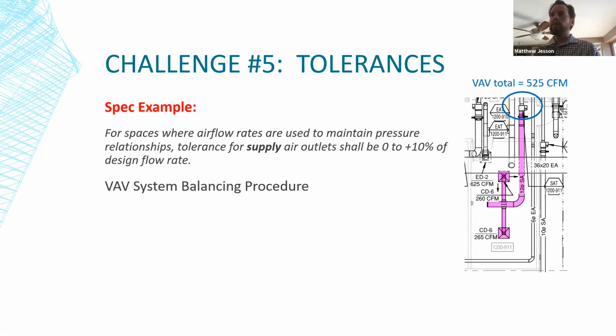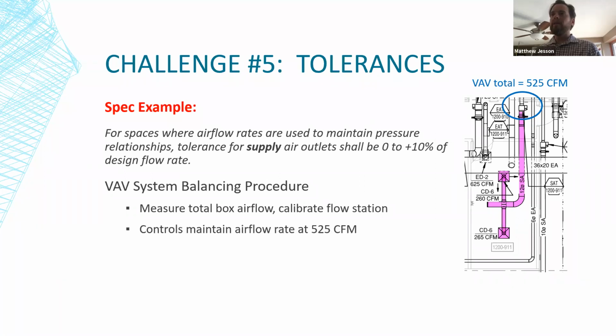The VAV system balancing procedure is, first of all, you measure the total airflow for this box, and then you calibrate the flow station in the box. So once that's done, the controls will maintain that airflow rate of 525 CFM. But of course, it's not perfect. It's going to vary a bit, maybe 510 to 540. It might be even tighter than that, but let's just say it's 510 to 540.